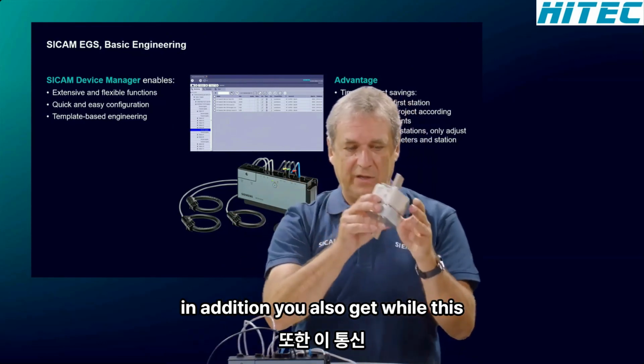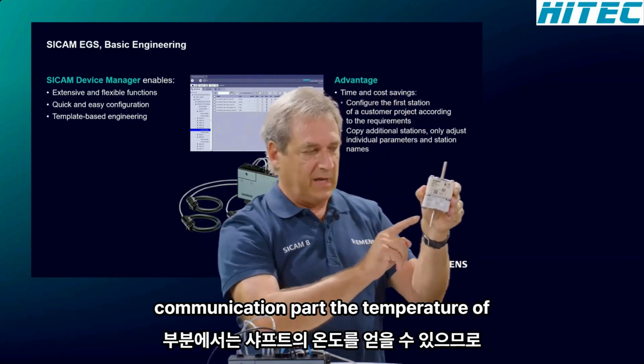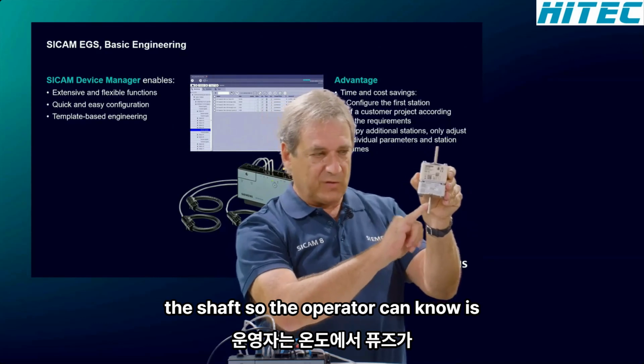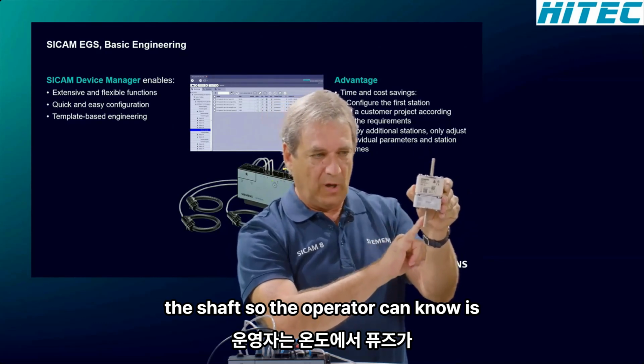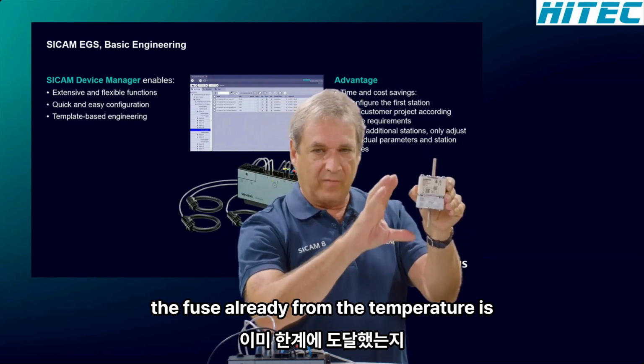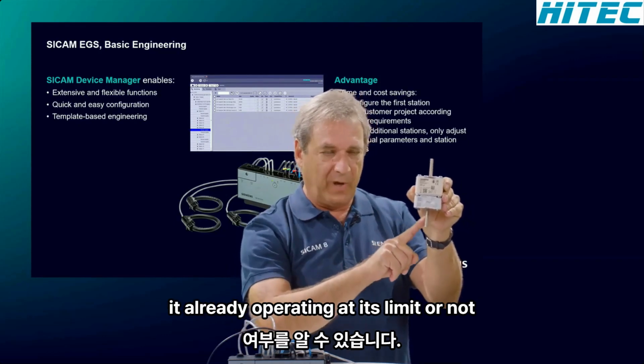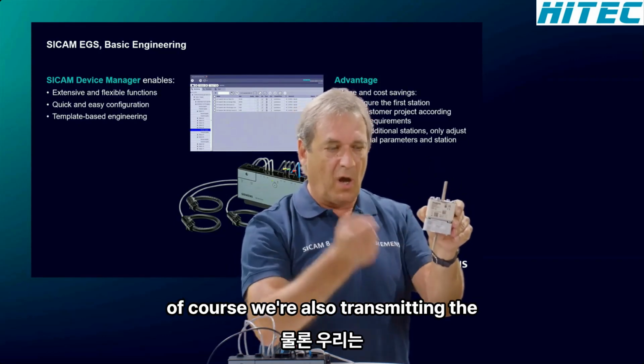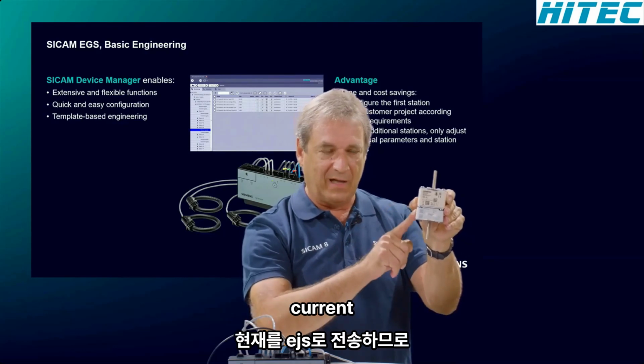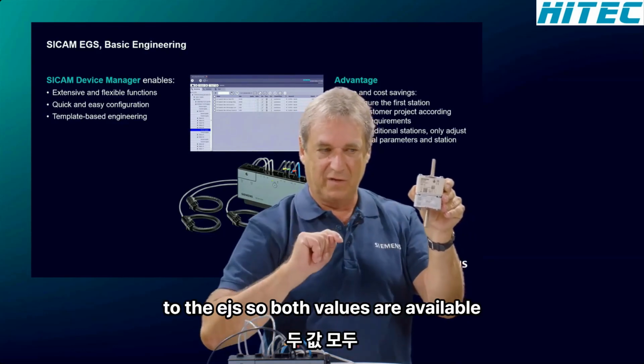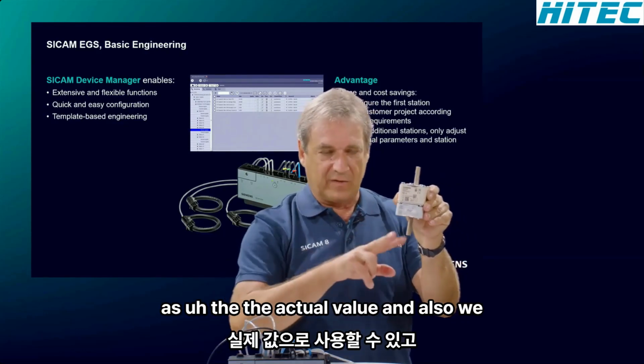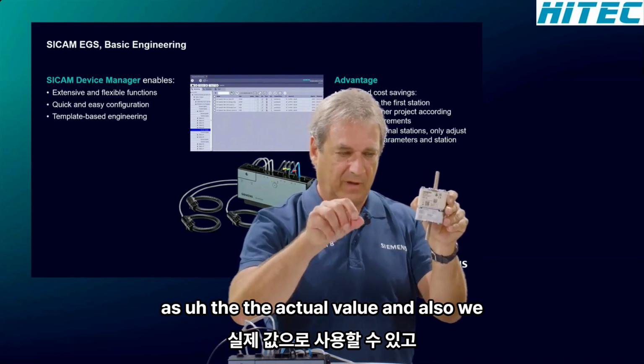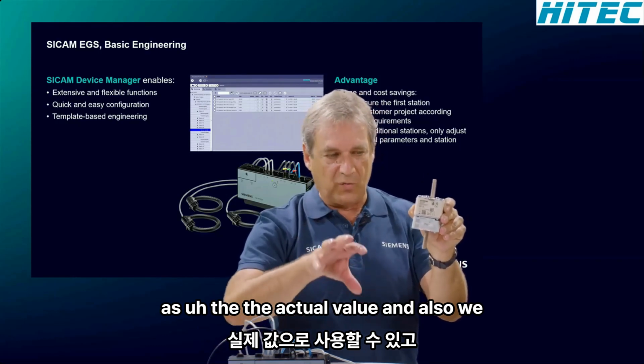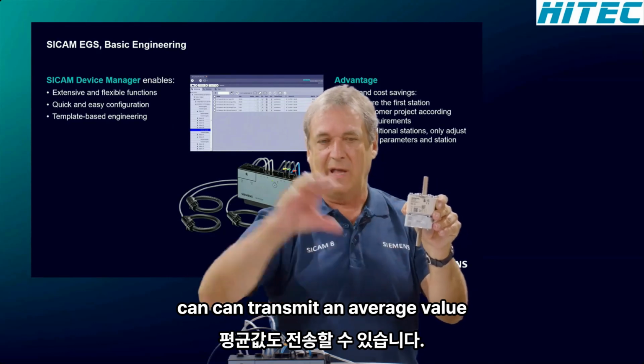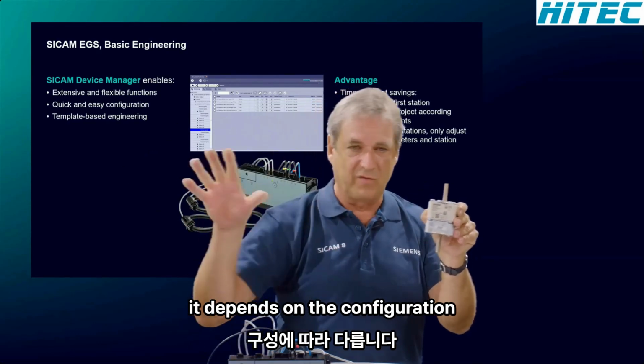In addition, you also get via this communication part the temperature of the shaft. So the operator can know, from the temperature, is the fuse already operating at its limit or not? Of course, we're also transmitting the current to the EGS. So both values are available as the actual value, and also we can transmit an average value. It depends on the configuration.